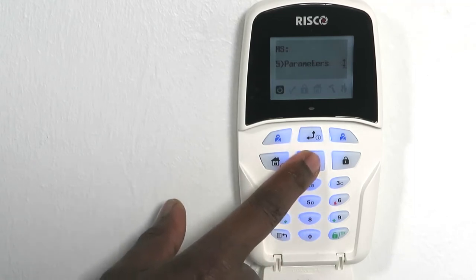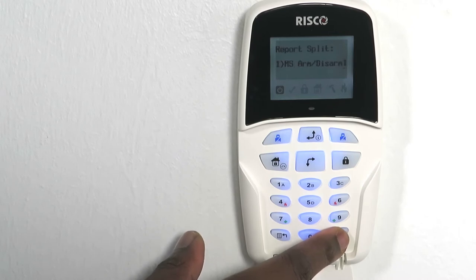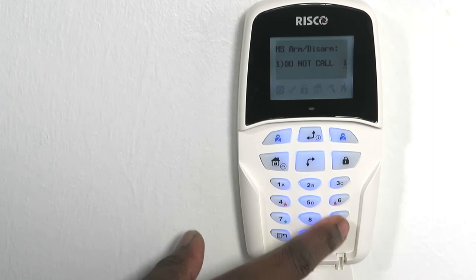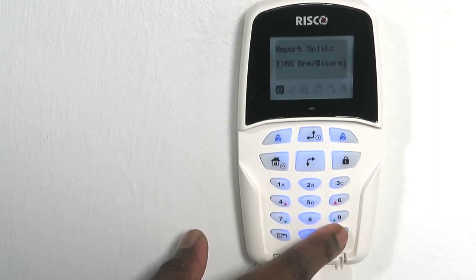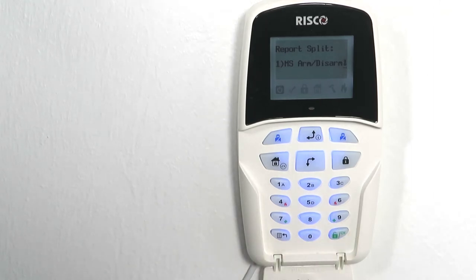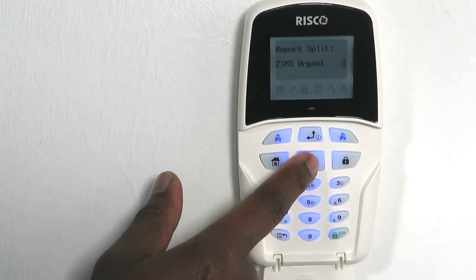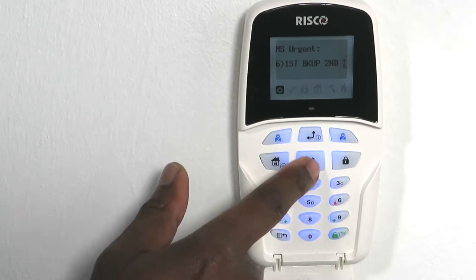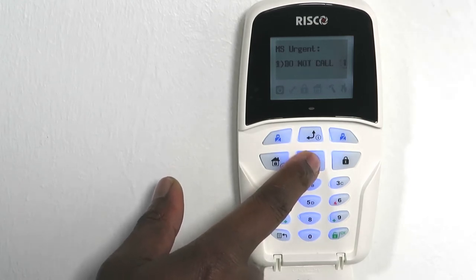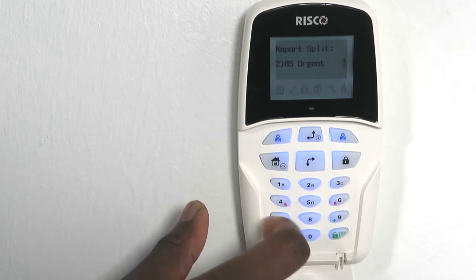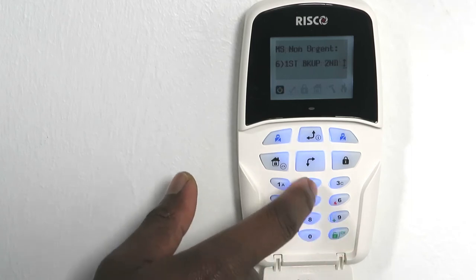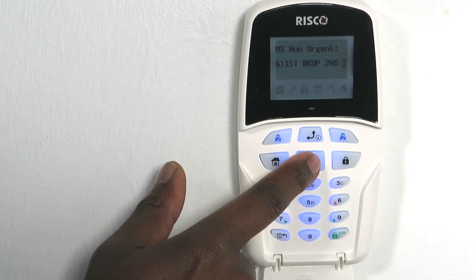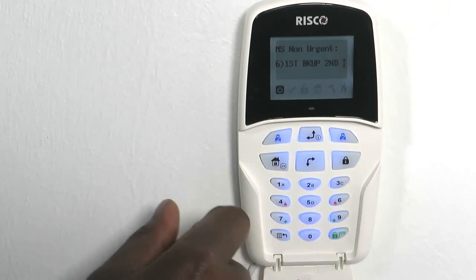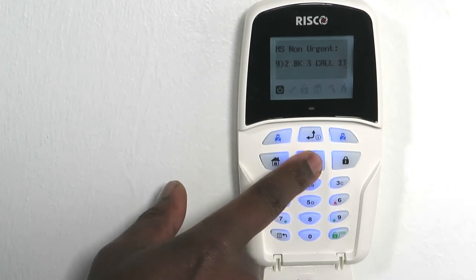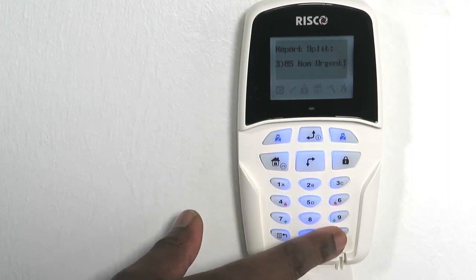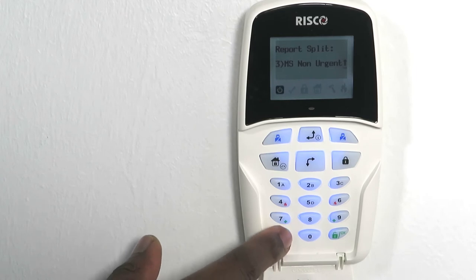Scroll down to Report Split and press OK. Select MS Arm Disarm by pressing OK. Scroll to Call First and press OK to select. Scroll to MS Urgent and press OK. Scroll to Call First and press OK to select. Scroll to MS Non-Urgent and press OK. Scroll to Call First and press OK to select. Press the menu button 3 times to go back to the main programming menu.